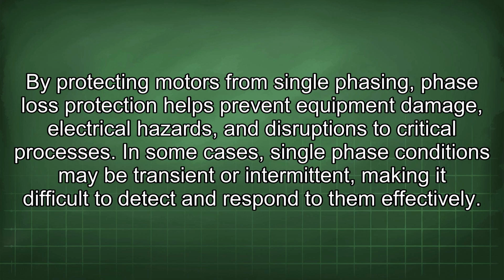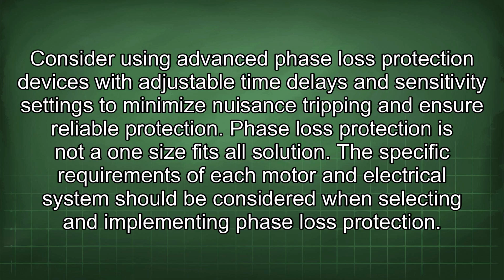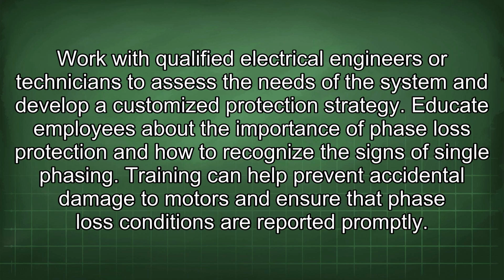In some cases, single-phase conditions may be transient or intermittent, making it difficult to detect and respond to them effectively. Consider using advanced phase loss protection devices with adjustable time delays and sensitivity settings to minimize nuisance tripping and ensure reliable protection. Phase loss protection is not a one-size-fits-all solution. The specific requirements of each motor and electrical system should be considered when selecting and implementing phase loss protection. Work with qualified electrical engineers or technicians to assess the needs of the system and develop a customized protection strategy.